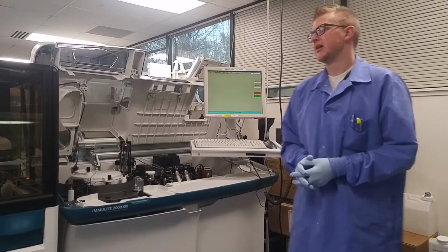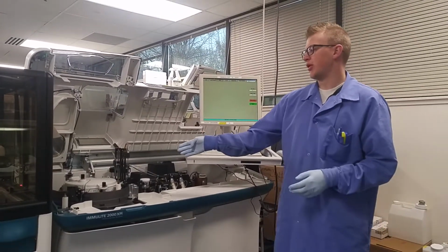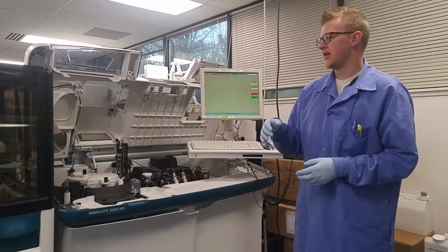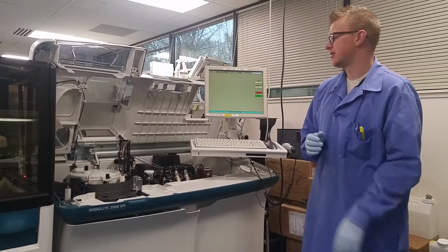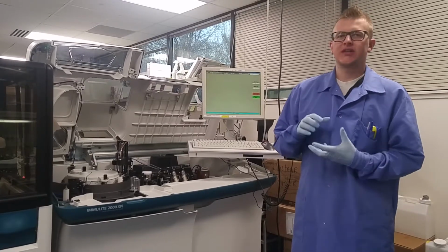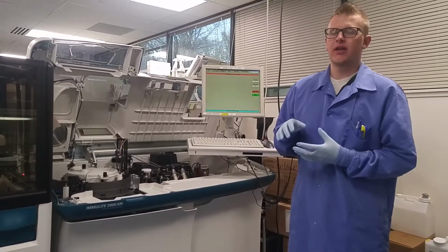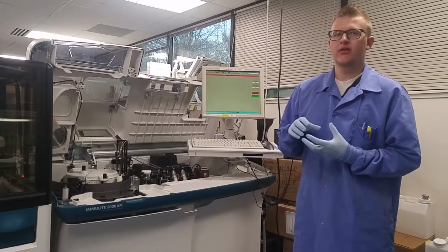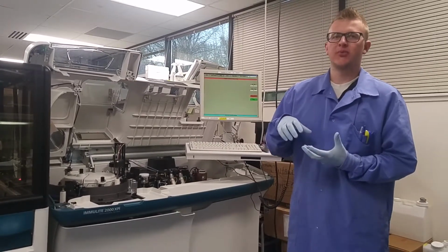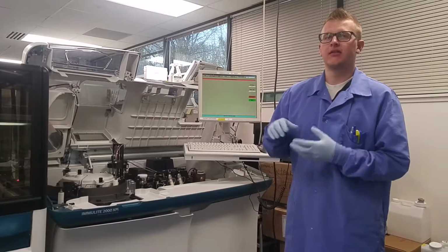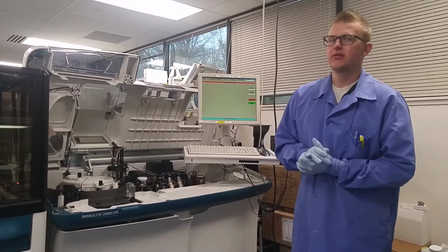So what Clot Prime does is it will take this sample probe, and it's going to purge anything from the internal, inside of the probe, the internal workings. It will also purge the transducer cavity of all fluid in case a Clot was in that reservoir. Once it's all purged, it will then signal me to allow me to refill it, and we'll move on to the next step.